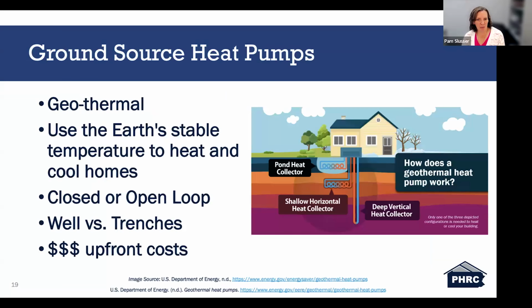And then we have our ground source heat pumps. This is commonly referred to as geothermal systems, you might hear them called. These take advantage of the Earth's stable temperature to heat and cool the home. They're categorized, you can have a closed or an open loop. They're installed horizontally, vertically, or in a pond or a lake. That's where they bring the heating from the Earth's stable temperature into the home. So the type that you would use would depend upon the land that's available, where the home is being built, whether it's soil or rocky ground at installation as well, because that's going to dictate what you might use. So a little background on it.